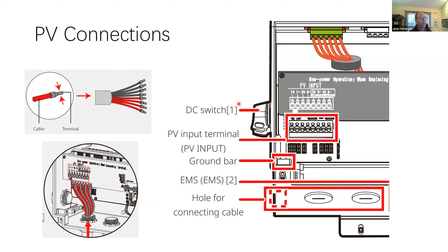The example here is showing all of the, in this case, 4 pairs of PV input circuits, all having the wire ferrules on them, all plugged in, with illustration of the ground bar again. We're showing the same stuff here in graphic form. There is a DC, so a PV disconnect switch that's lockable. And that's it on the PV side.